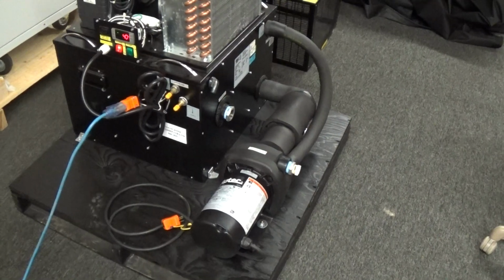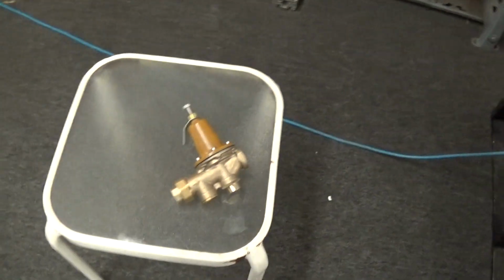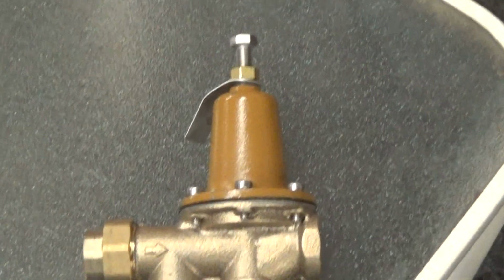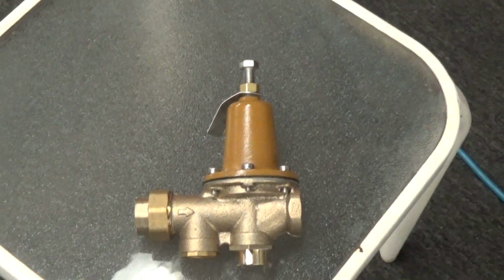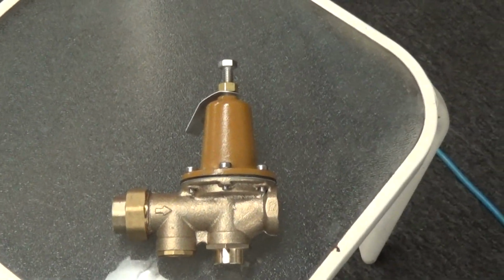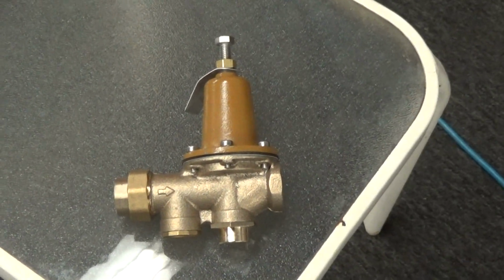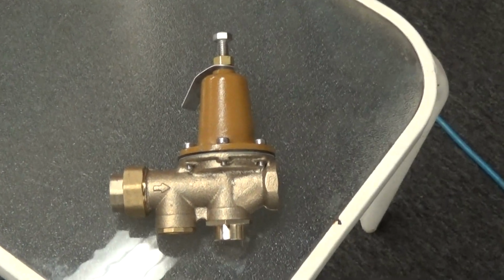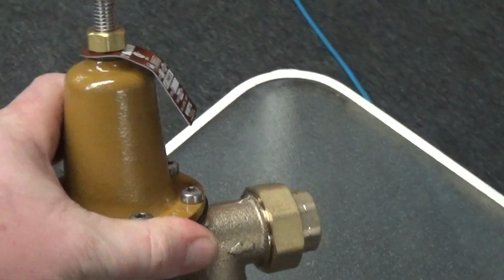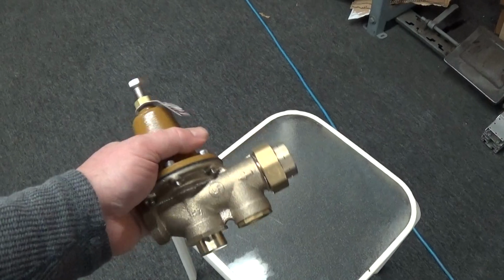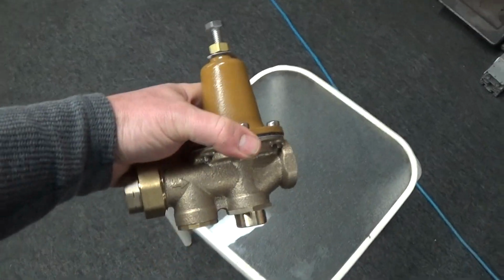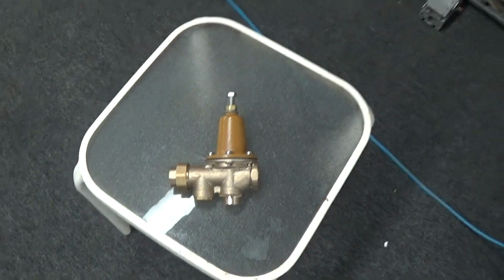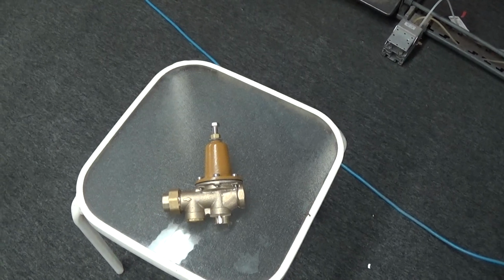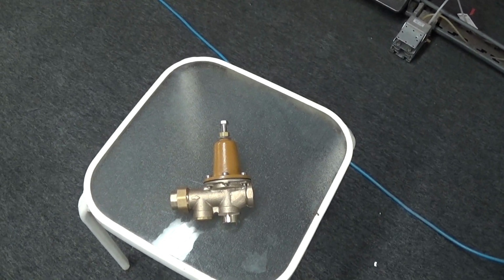Lastly, when you do your piping out to your reservoirs, you're going to want to have some type of pressure regulator on each one of your fermenter or brite tanks, obviously along with your own controls and solenoid to control the inlet of the cold glycol going into your tanks to control each individual tank temperature. This is just one example of a 3/4 inch pressure regulator. We want to have something like this on each one of your vessels. This one can be adjusted down to 15 psi. So that will protect the jackets in your tank, and it helps maintain the pressure that's going to be in your supply line.